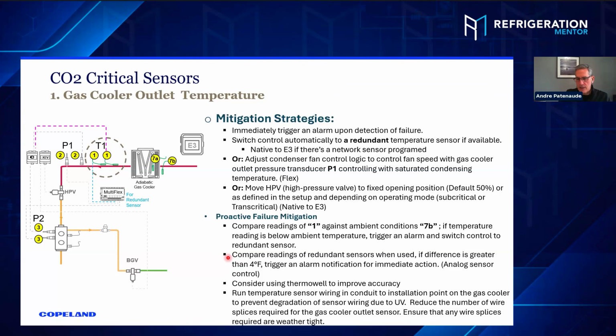Absolutely. And another thing you can do is compare the readings between redundant sensors. If you do have redundant sensors, you can compare them, and if they're greater than 4 degrees apart, send an alarm, have someone come in, figure out which sensor is off and change it so that you protect yourself in the future. I'm spending more time talking about these now, but a lot of these mitigation strategies you're going to see repeated a few more times. So if you get them now, your thought process will be similar for other sensors. That's what's important. Consider using a thermal well.